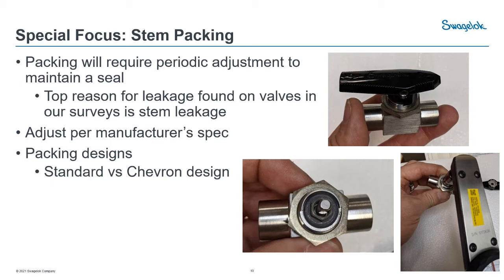Here's an example using one of our 40 series ball valves. If you remove the handle, you'll see a hex flat underneath — that's your packing nut adjustment. There will be a manufacturer torque spec, and you use a torque wrench to torque it down to the specified value. Stem leakage is the number one reason we find for leakage on plant surveys. It's a spot where many of us set it and forget it, but that seal wears every single time you actuate the valve. After months and years of use, you'll eventually need a little adjustment.